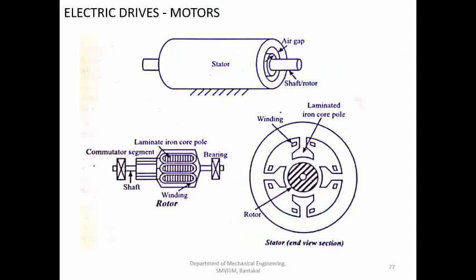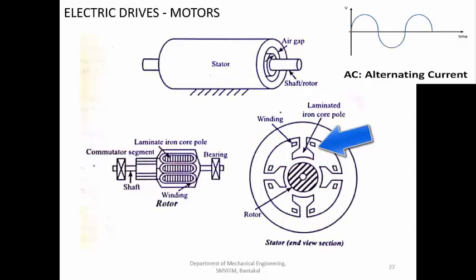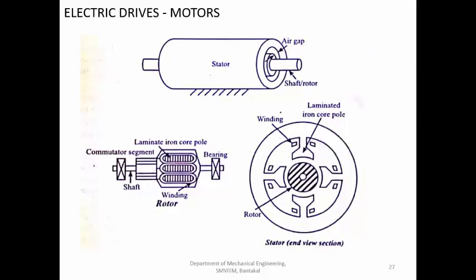In the DC motor, we have a commutator and coils. The commutator continuously changes the direction of current flow through the coils. In AC, we supply current to the stator, and AC current can do induction — whatever flux is generated in the stator coil, a reverse flux is created in the rotor conductors, and these two interact to produce rotation. But in DC, this does not happen. As the rotor rotates, we continuously change the direction of current by artificial means using the commutator, which is divided into two parts connected to different coils, ensuring the correct magnetic polarity so rotation always occurs in the same direction.